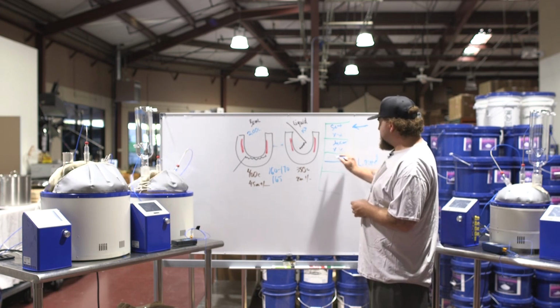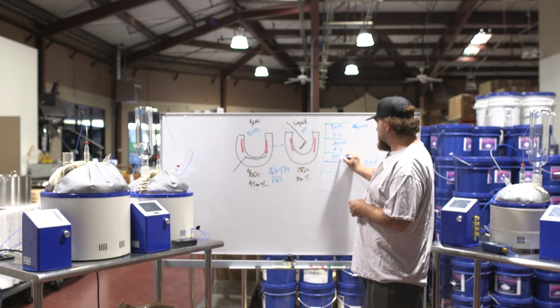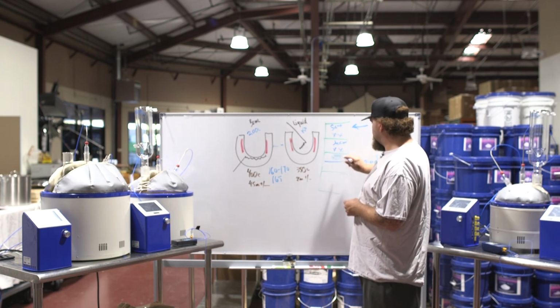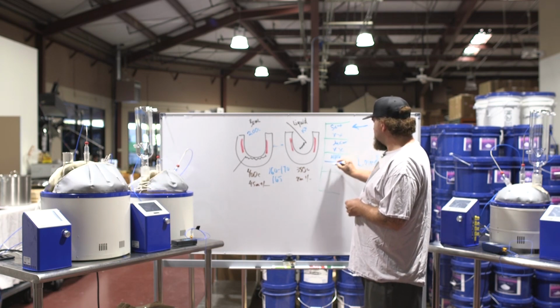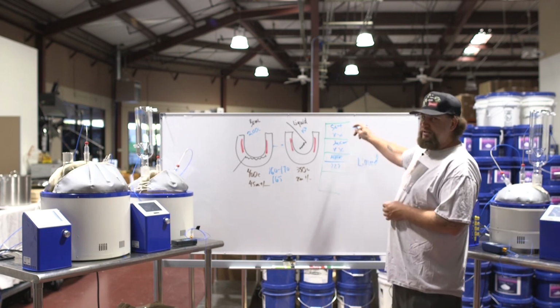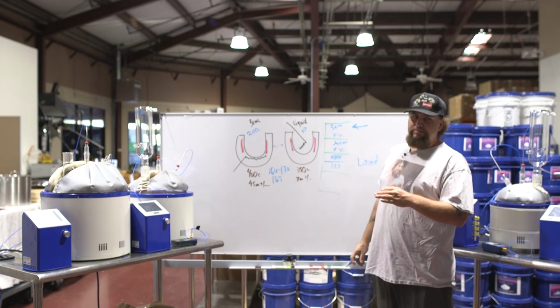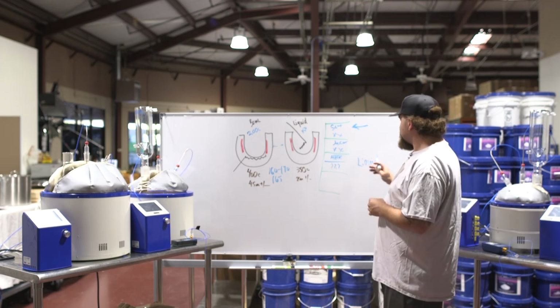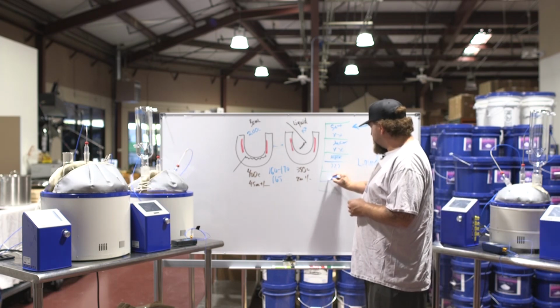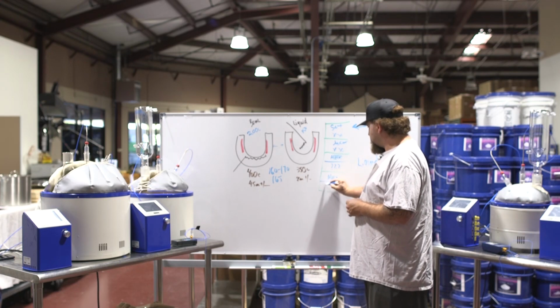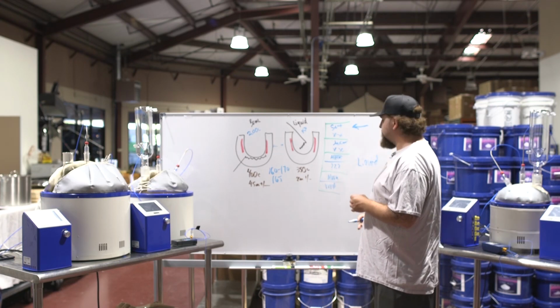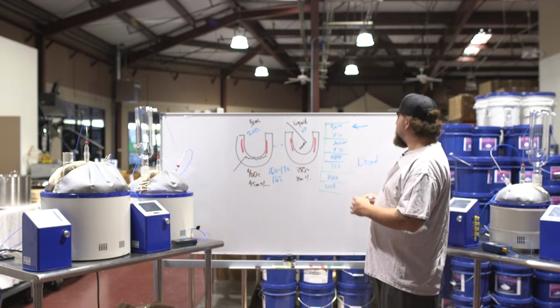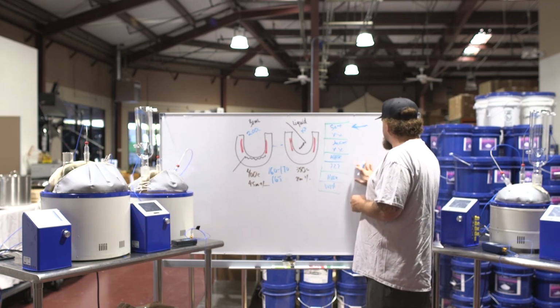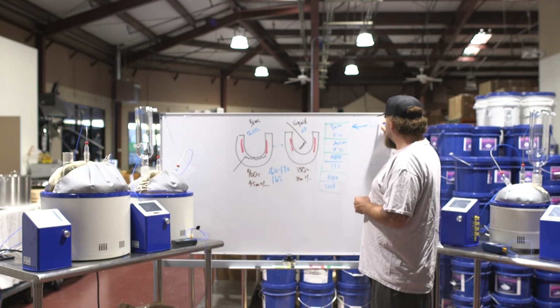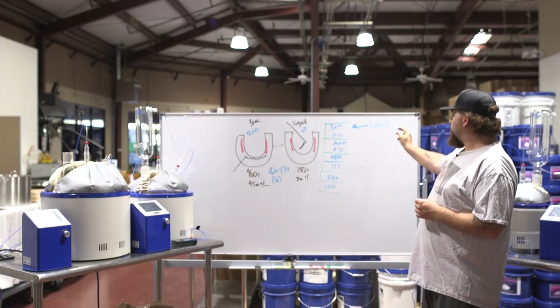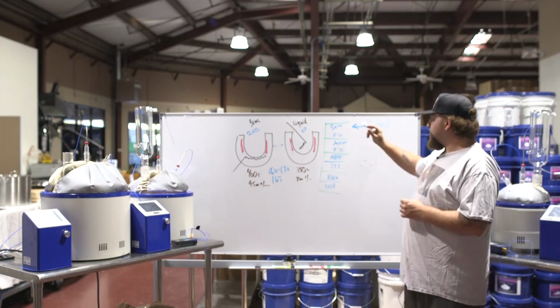So now this becomes arbitrary. I'm sorry, this is the alarm. And this becomes arbitrary, which means that whatever you set this point at, this will tell you what that temperature is, guaranteed without a doubt. And then right here you have your vapor. You have your alarm, and you have the vapor temperature. This is the exacting temperature. So if you switch the probes, what's going to happen is this set point will actually be liquid. So the liquid probe gets changed, and now it's reading from the liquid side.